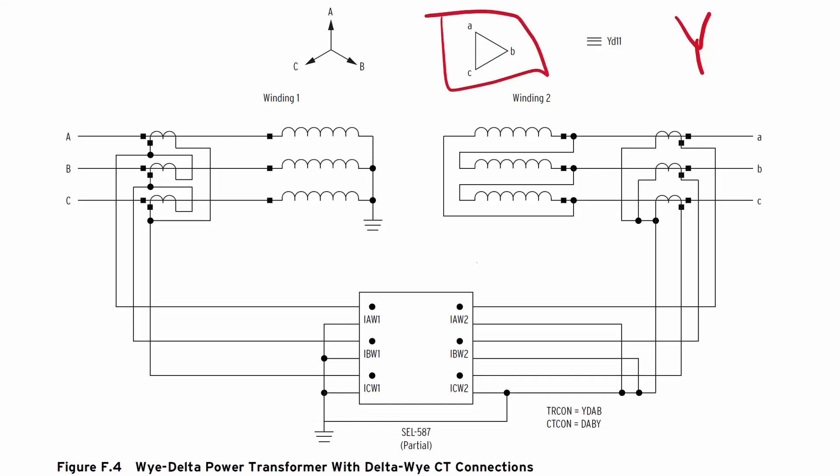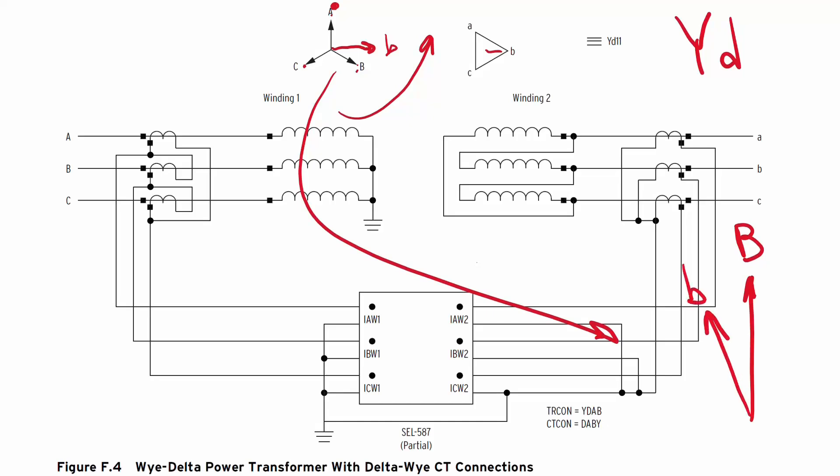So the secondary is a delta with a little d. And then what is the clock shift? Well, if you look, B comes straight out to the right. So let's just use that as an example. It's just the easiest way to look at it. So this is little b. We're comparing same phase. And, well, lo and behold, little b is, if this is rotating in this direction, if you're standing right where A phase is, what comes first? Big A and then big B and then little b. I mean, big A then B then C, because this whole clock's rotating A, B, C. So you would see little b first and then big B. And if you redraw this as a clock shift that actually looks straight, you would have big B. Remember, big B is always going to be at 12 o'clock. So where is little b with respect to that? We're just going to redraw it right here. Well, little b is going to be right here. This is little b. That means that little b is at 11 o'clock. And that's how you get these clock shifts.